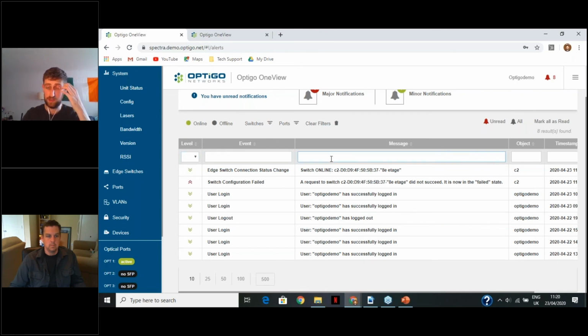So if we want something specific, if we want to look in and see when a device went up or went down, anything along with the message, especially if we want to see whether something has been reoccurring or occurring regularly, which is where this becomes quite strong as well. If something happens and looks a bit suspicious, one of the first things we want to check is, has this happened before? Is it a once-off or is this recurring? Especially with something like a device going up and down, over the course of time with heat in the room, the cords can wiggle themselves out due to expanding and contracting. So they can cause small things like this.